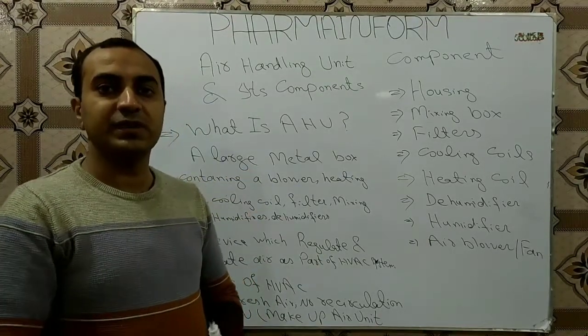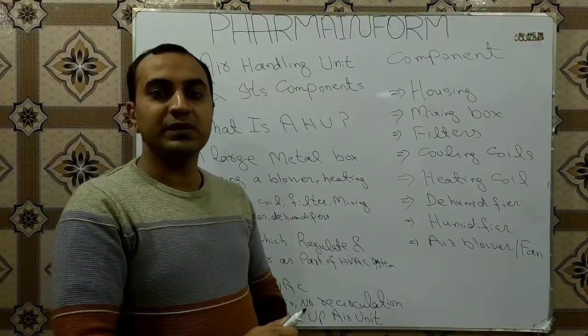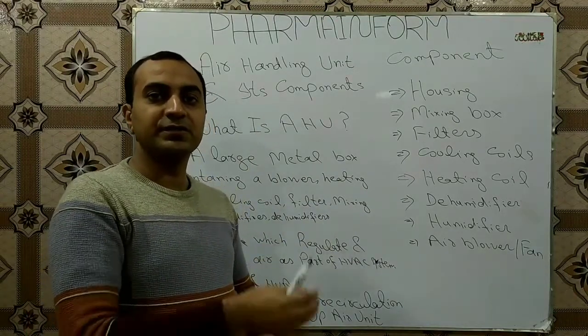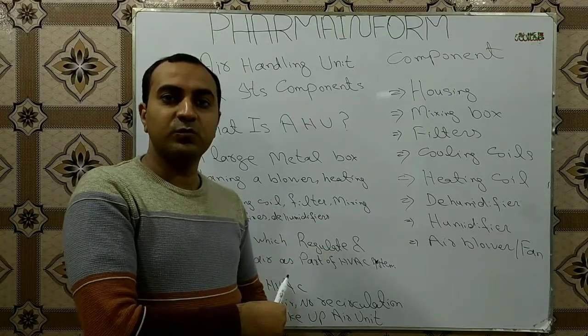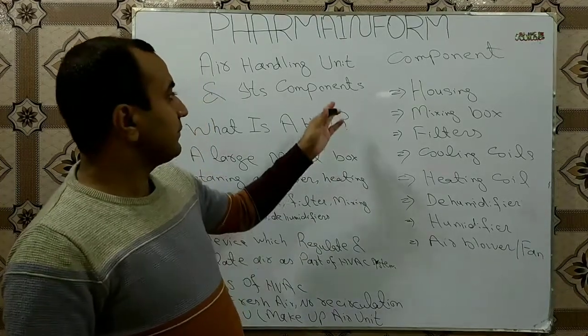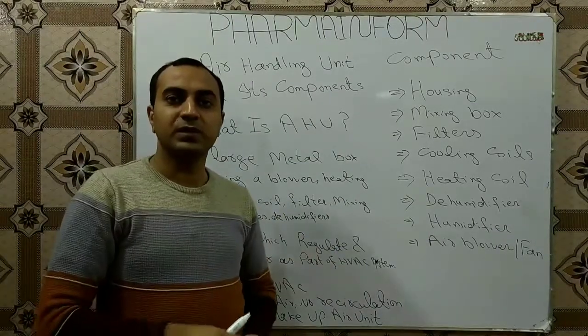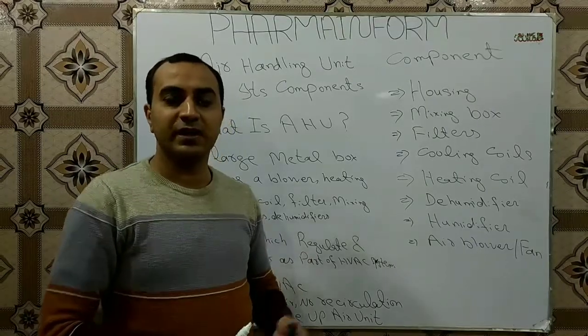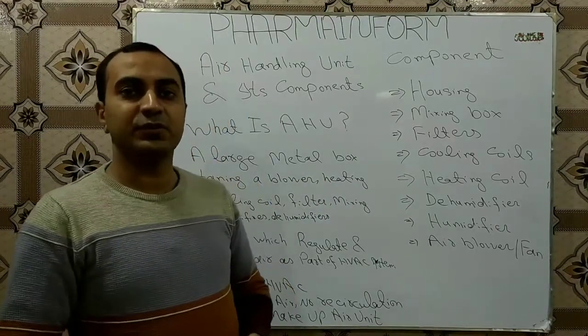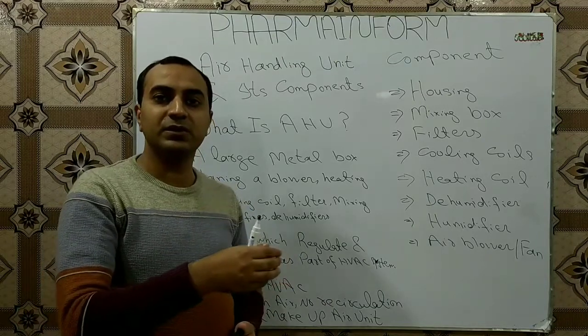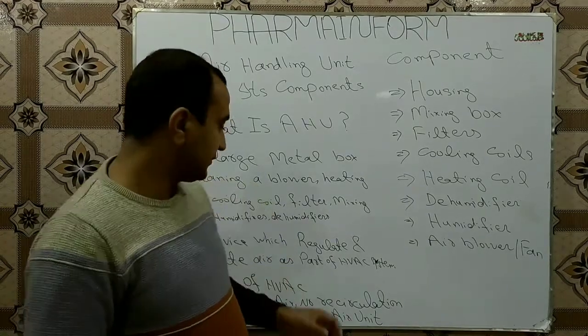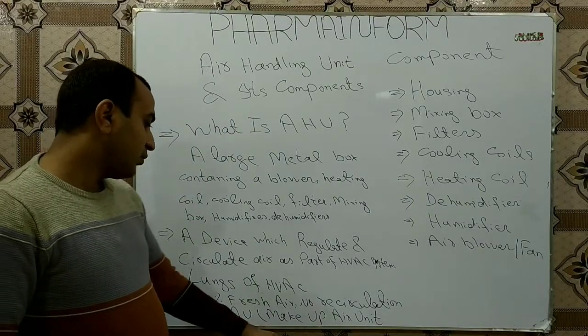AHU also reconditions the air which comes from the rooms. AHU takes fresh air from the outside environment, conditions it, supplies it into the room, and then this air from the room comes back again into the air handling unit for reprocessing. This type of air handling unit usually consumes 10 to 15 percent fresh air, and the remaining air is taken from the room as return air and reprocessed.